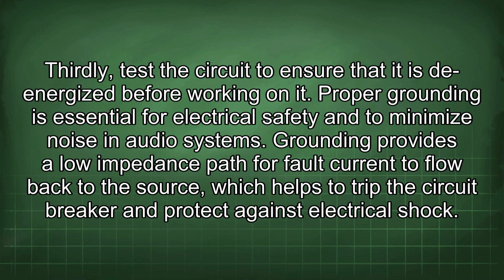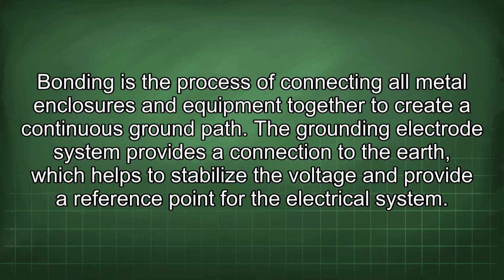Proper grounding is essential for electrical safety and to minimize noise in audio systems. Grounding provides a low impedance path for fault current to flow back to the source, which helps to trip the circuit breaker and protect against electrical shock. Bonding is the process of connecting all metal enclosures and equipment together to create a continuous ground path.